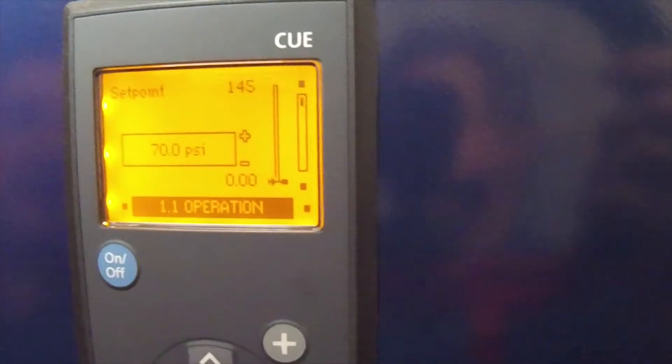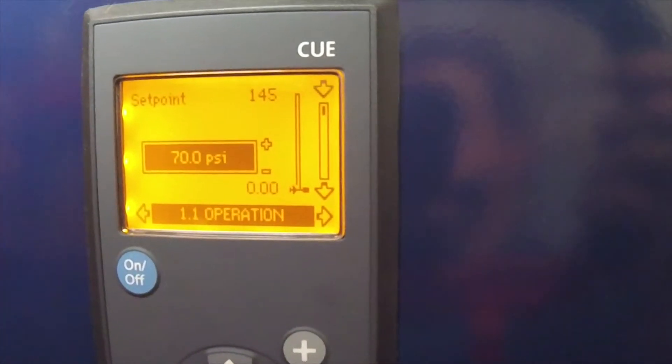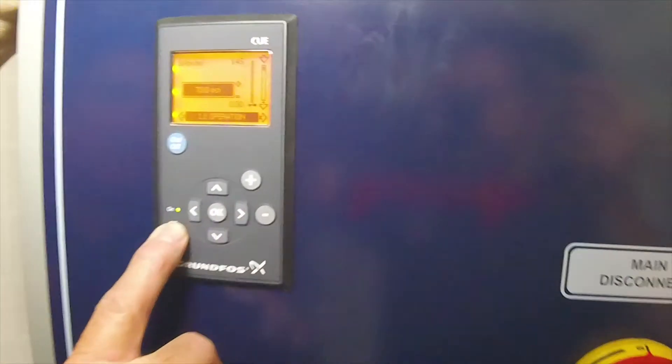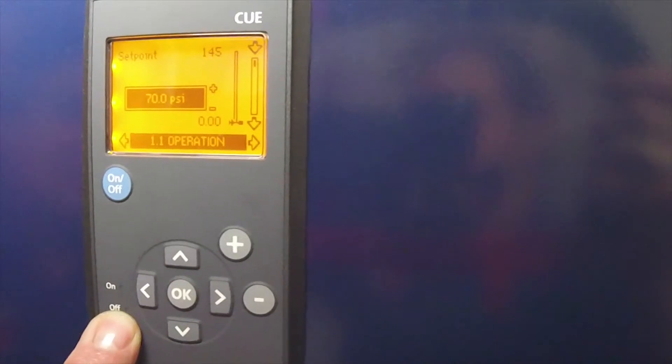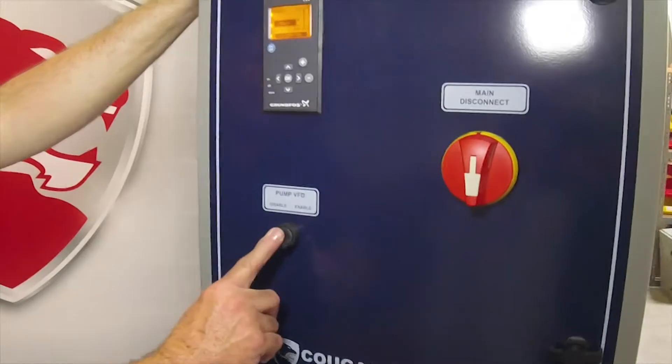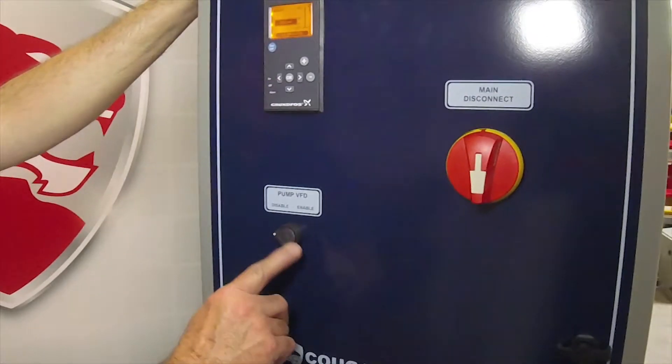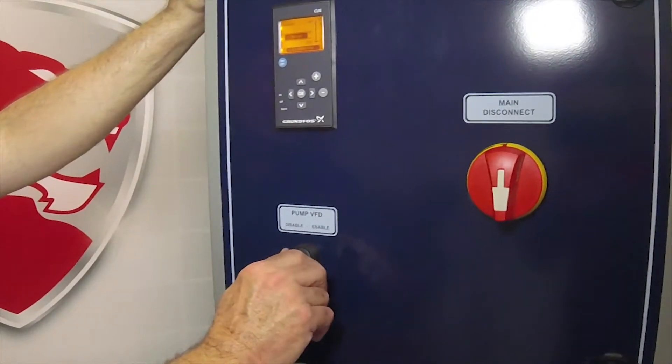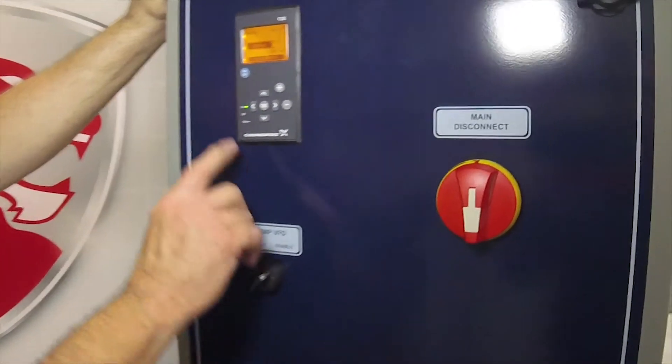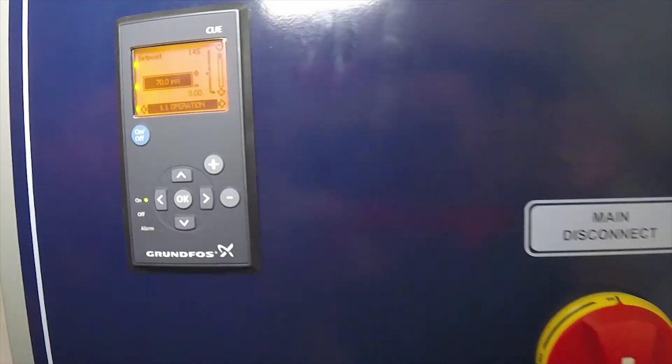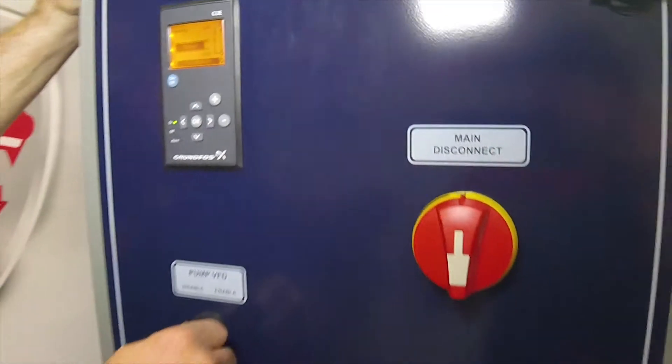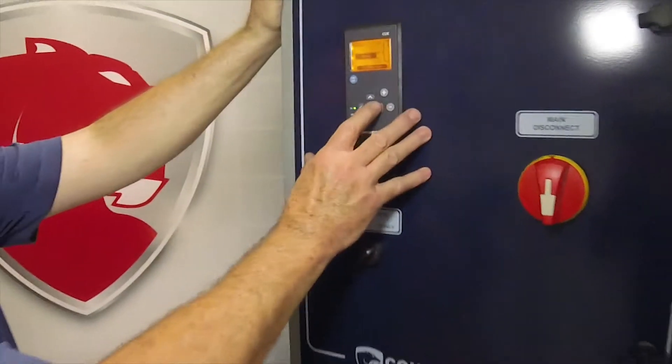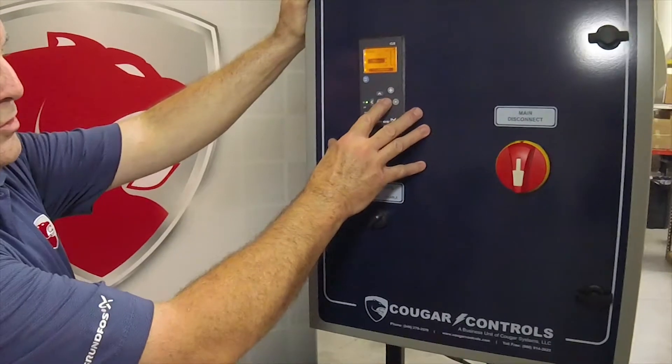Hit OK and now you have a new set pressure. Now you'll notice this green light is blinking. The green light blinks when the drive is disabled. We have a disable/enable switch down here. When you turn this to enable, you'll notice the light goes solid and now the pump is operating.